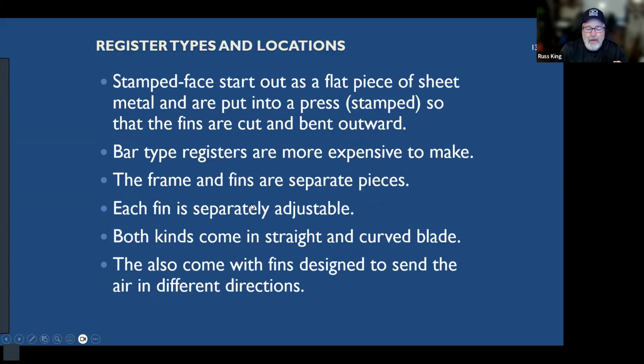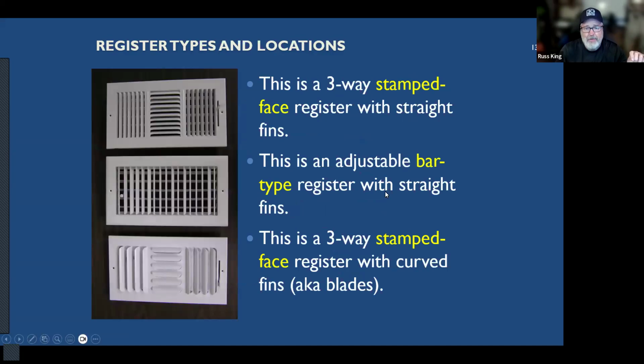I just want to hit a couple more important things. When we talk about registers, there's two basic types: stamp faced and bar type. Bar type are more rare. Stamp face are very common. This is a stamp face and this is a stamp face. A stamp face register starts off as a flat piece of sheet metal and it gets stamped. A big machine stamps it like that, and it cuts the blades and presses them out. It's one piece of metal. A bar type has a frame and then the fins are individual pieces that get inserted. The important thing to understand about this is these have much better airflow.